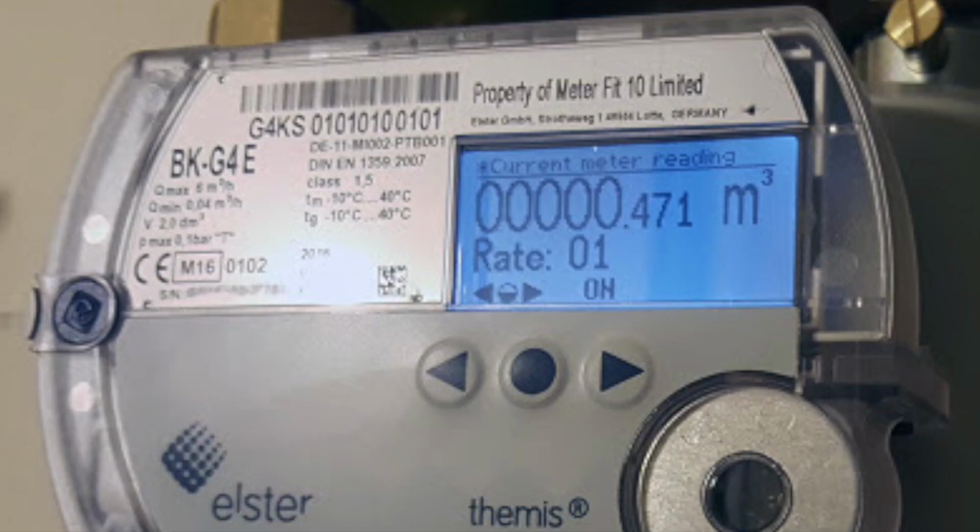So again, after a short time the display will go blank again. This is always to save the battery. So again, after 1 minute and 30 seconds of the 2 minutes, or 120 seconds of this test period, press any of the navigational buttons again to re-wake the display. Then again, we've got to wait till we nearly get to this 2 minutes before we can take our final and second reading. So once we get up to the 2 minutes, we stop the stopwatch and take our second reading.